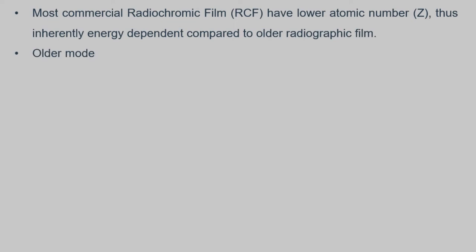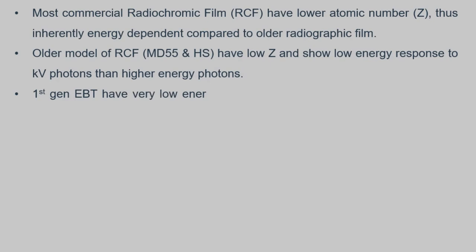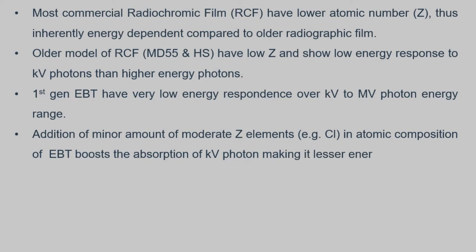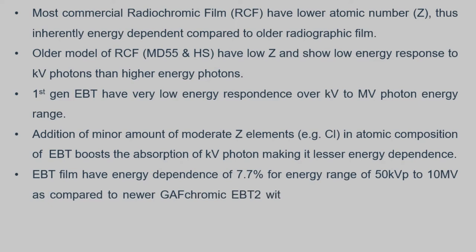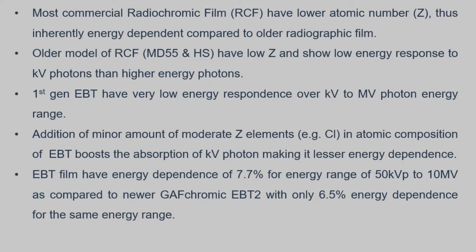Most commercial RCF have lower atomic number that is inherently energy dependent compared to radiographic film. Models of RCF such as MD55 and HS have low Z and show low energy response to kV photons compared to higher energy photons. First generation EBT has very low energy dependence over kV to MV photon energy range. Addition of minor amounts of moderate Z elements, for example chlorine, in the atomic composition of EBT boosts absorption of kV photons, making it less energy dependent. EBT film has energy dependence of 7.7% for an energy range of 50 kV to 10 MV, compared to GAFChromic EBT2 with only 6.5% energy dependence for the same energy range.